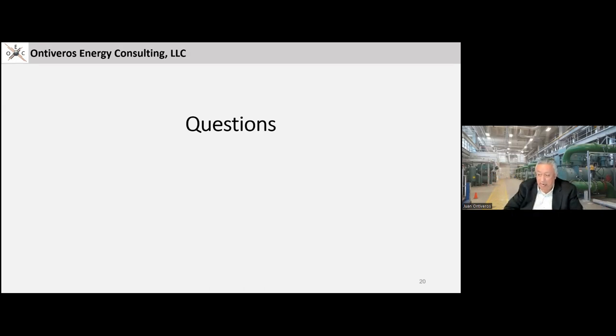And so I think that, for example, cooling towers, I'm gonna go back to cooling towers. We did a life cycle cost analysis for a 60,000 GPM tower, a big tower, a 6 cell tower that we put in there, Chase. And when we did the life cycle cost analysis, we determined that the tower that we chose was more expensive in first cost, but because of its efficiency over a 30-year period was cheaper. So you can dramatically change how you think about doing things.